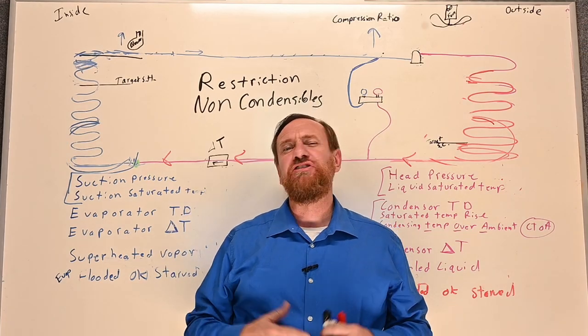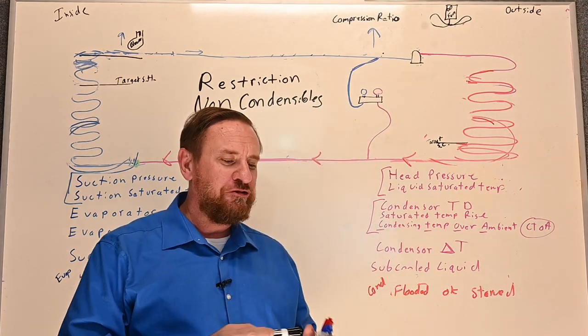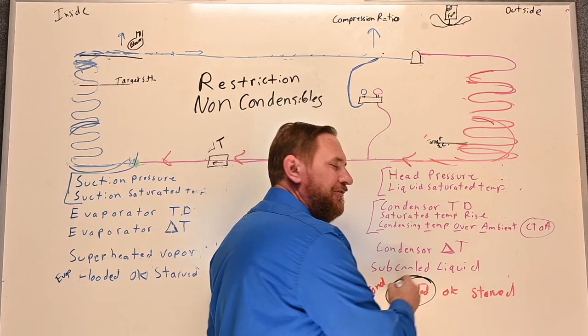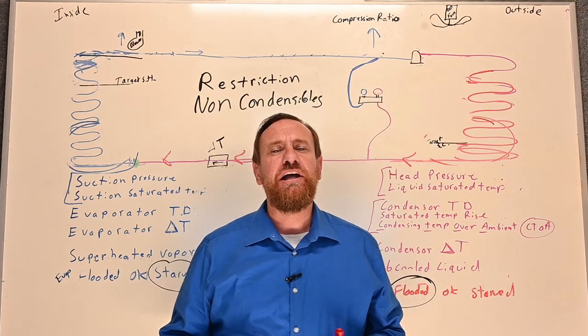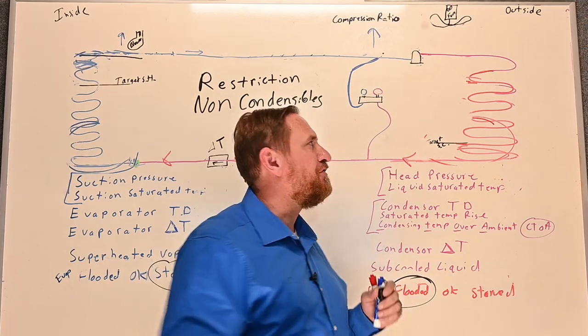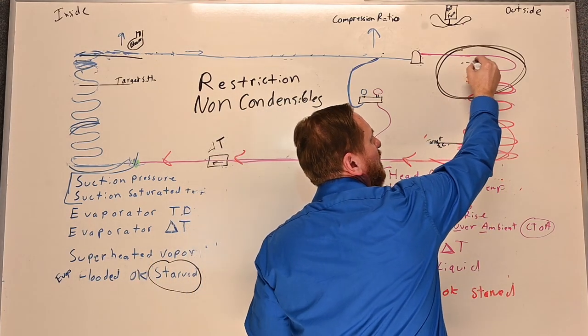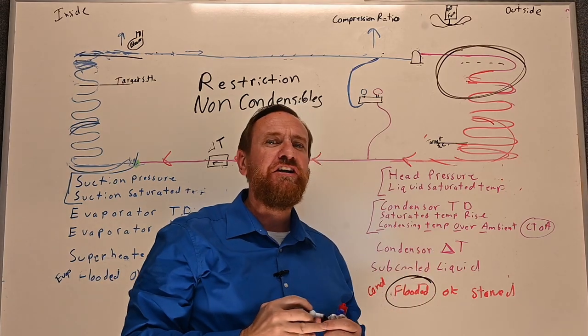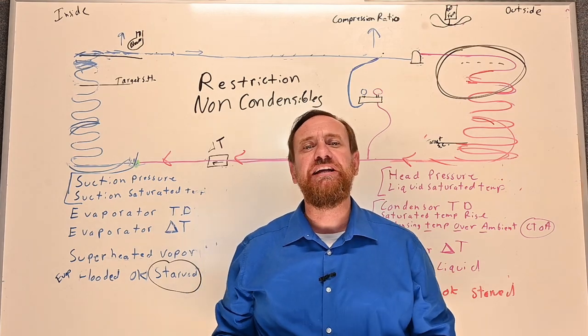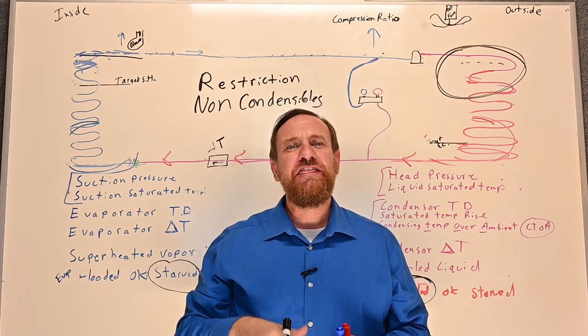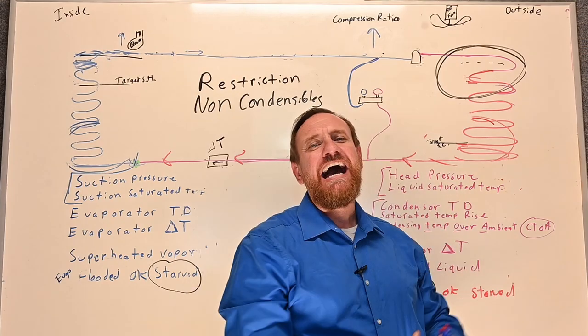With non-condensibles, looking at superheat and subcooling gives us the same effects as a restriction — it looks like the condensing unit is flooded and the evaporator coil is starved. Non-condensibles are impurities in the refrigerant that collect at the top of the condensing coil, in the desuperheating area. In a recovery tank with both pure refrigerant and non-condensibles, you could theoretically open the vapor side and the non-condensibles would draft out first since they collect at the top.